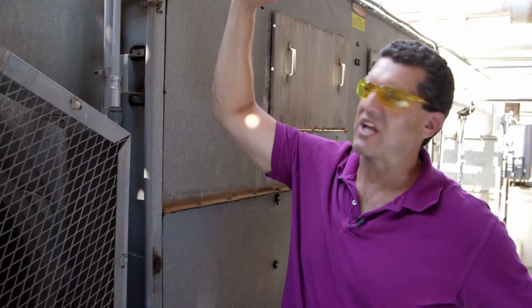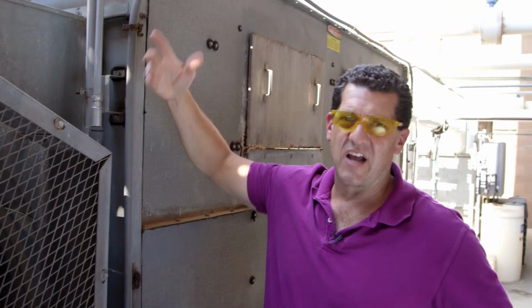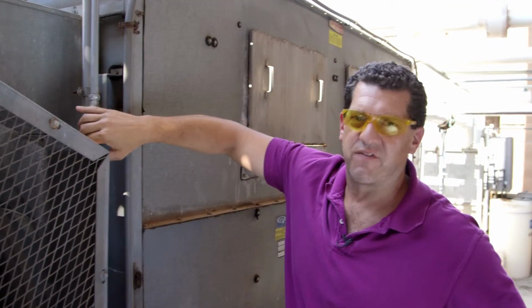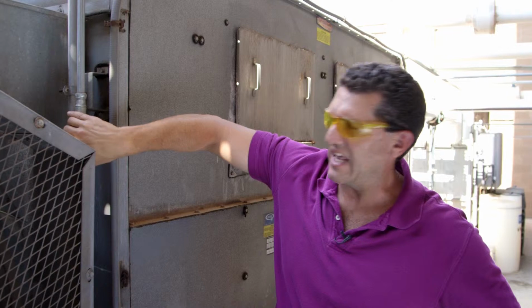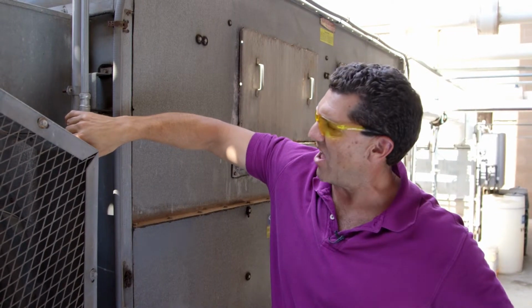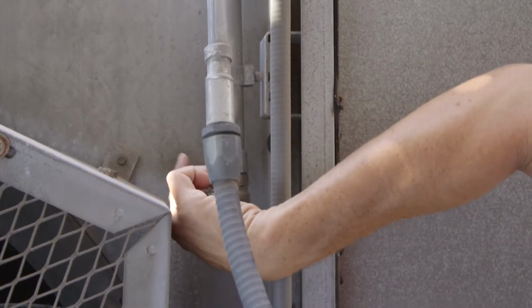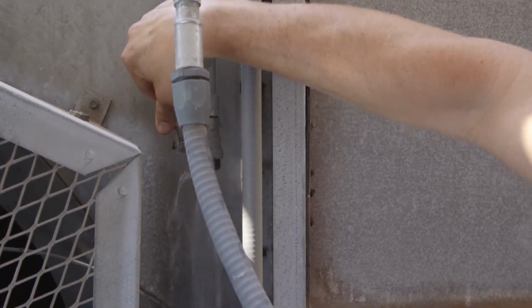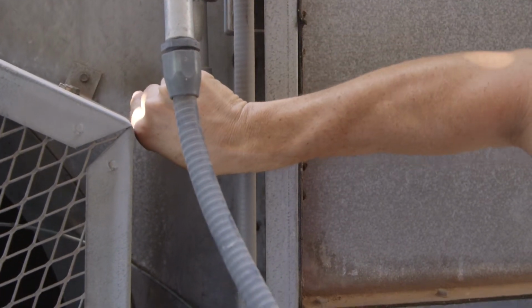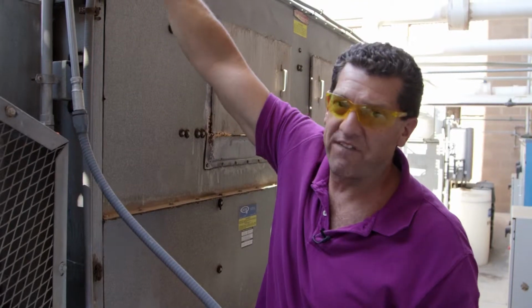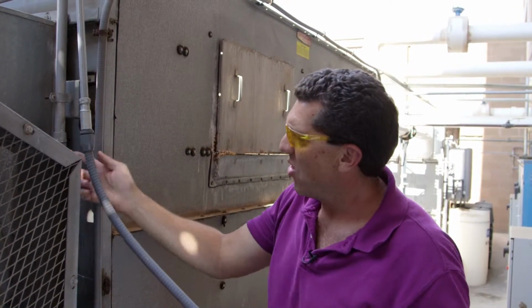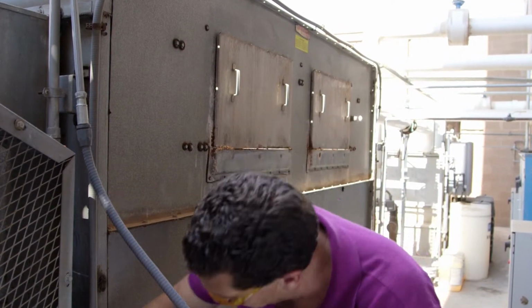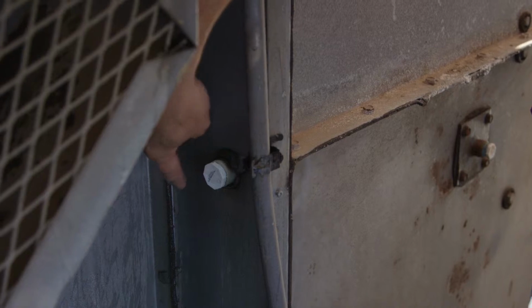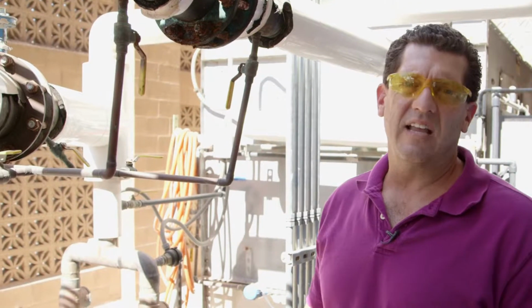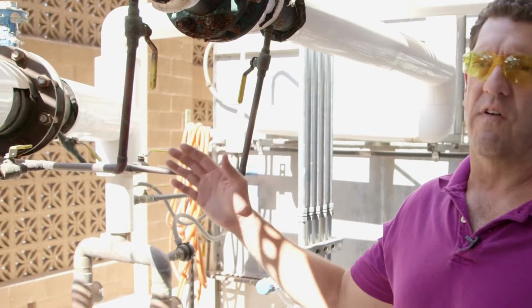So now we're on the other side, and all we do every time we come here is open up this valve, exercise it to let any dead water sitting on that line come on out. So the easy fix is to have this either capped off on the end of the distribution header or to have this line returned back into the tower. Your choice, whatever's easier. Another dead leg we found is where the crossover valve is.